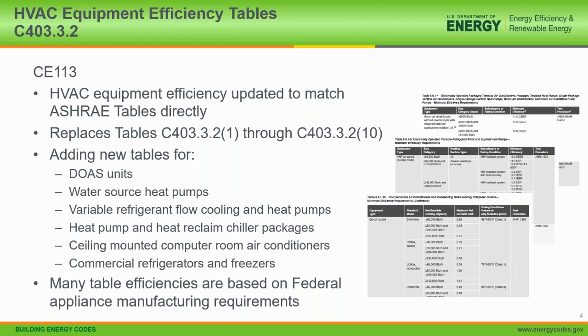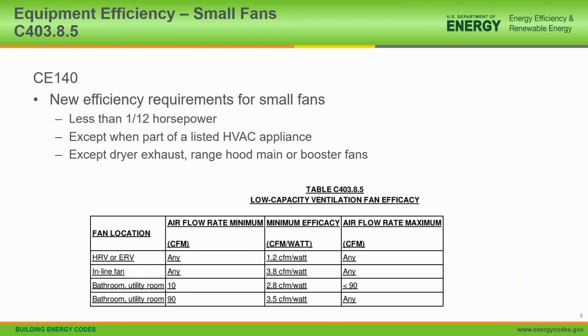CE 140 adds a new area of equipment coverage, actually ahead of 90.1, covering smaller fans under 1/12 horsepower, like your small bathroom fans. We do have some exceptions if the fan is built into a larger appliance, or your range hood. Dryer exhaust or range hood booster fans also are exempt. But basically, the HRV or ERV fans, any inline booster fans, and bathroom and utility room fans are now going to be covered. There is a similar proposal going into 90.1 as we speak, but it's not there yet.